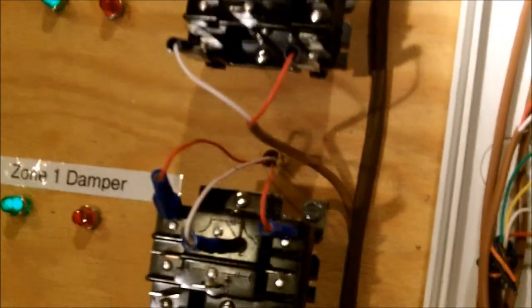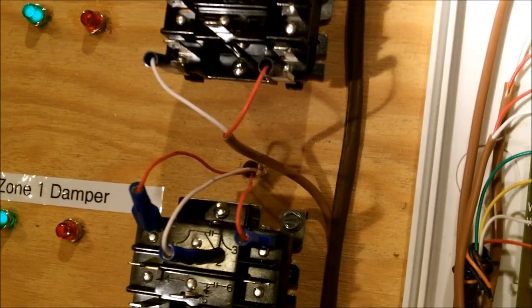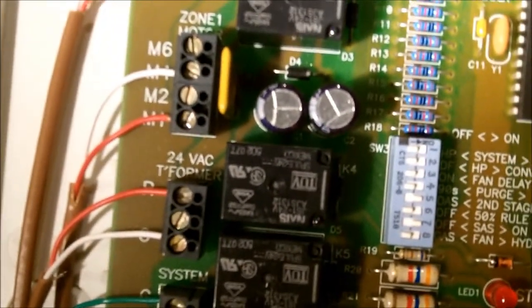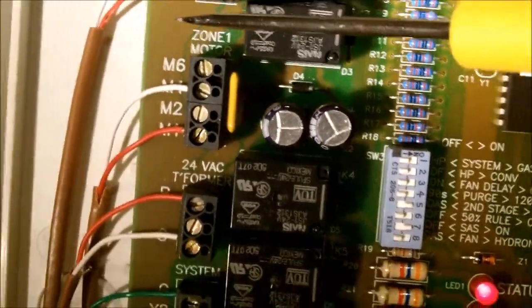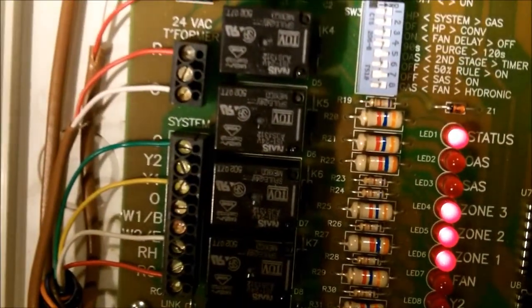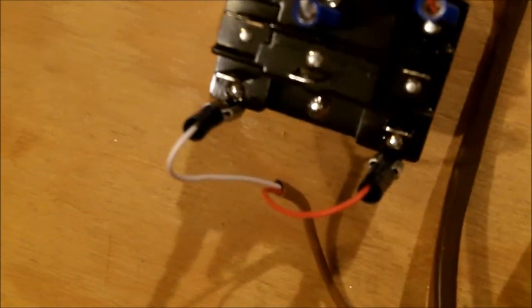Like I said before, I didn't have any dampers. Well, none that I can connect to this board. I do have a damper motor over there, and I'll show that here in a few minutes. But what I did is, you remember M1, M2, and M6 on your damper connections on the circuit board. What I did is I took my M1 for my common, ran it down, and supplied the relay with M1, and my M2 is my power open. So when it says, hey, I need power on zone 1, then what happens is it powers the relay, then it sends power.